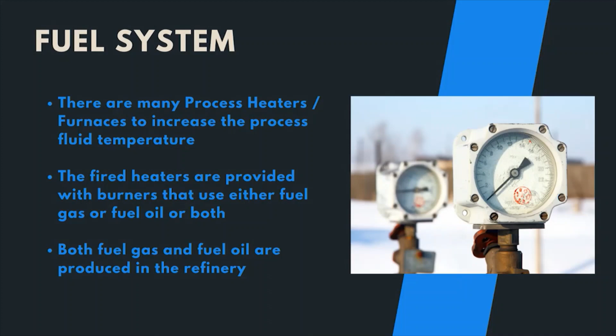So this can be done by burning fuel gas or fuel oil, and fuel gas and fuel oil are already produced in the refinery, but we need to have a system to regulate their flow, pressure, etc. Fuel gas can come through a fuel gas header. Similarly, fuel oil will also have a fuel oil supply header as well as a return header. If fuel oil is not kept moving, it can congeal and the line can get choked. So that is why we have a fuel oil return header, which will go back to the fuel oil storage tank, so that continuous movement will be there, and there is no possibility of the line getting choked.